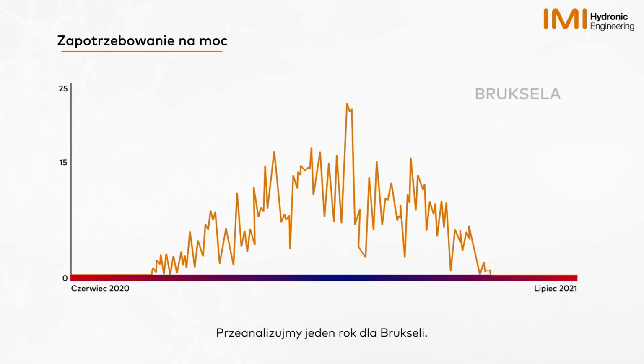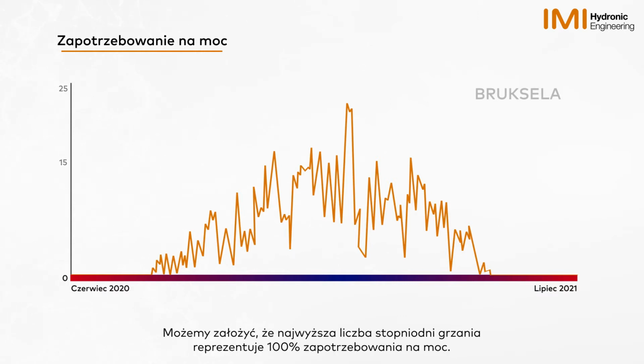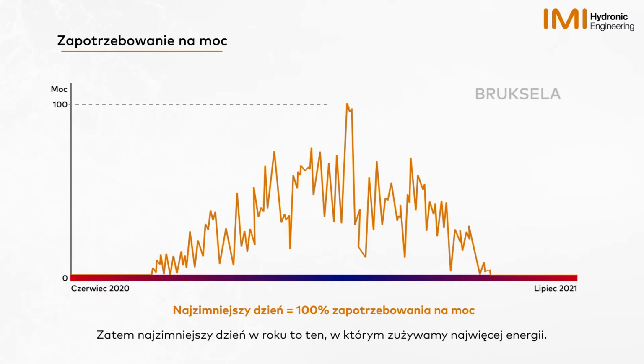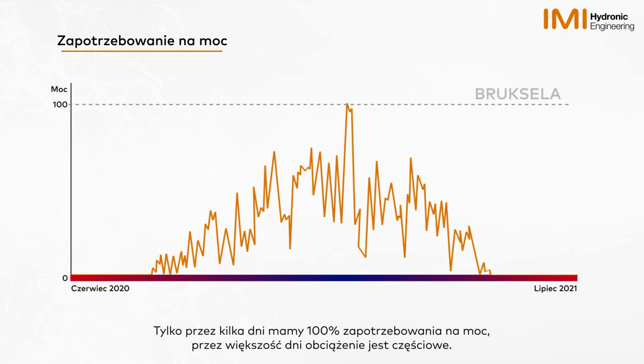Let's look at 1 year in Brussels. We can assume that the highest heating degree day represents 100% power demand. So the coldest day that year is when we use the most power. We only spend a few days at 100% power demand. The majority of days require only partial load.